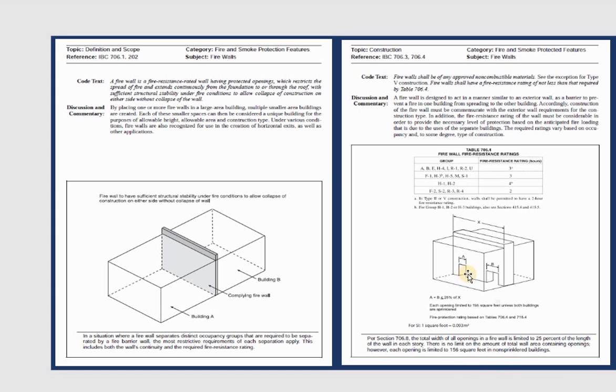Inside the building, if you have openings such as doors or windows, you need to design those openings carefully. Usually they measure the length of the wall versus the length of each opening. For example, if you have two openings A and B, you add together the length of A plus the length of B. That total must be smaller than 25% of X — the total length of the firewall. That's the rule: length A plus length B must be less than 25% of the total wall length.